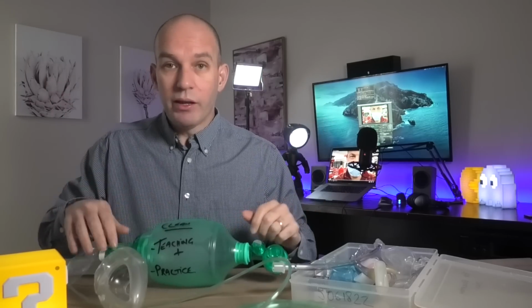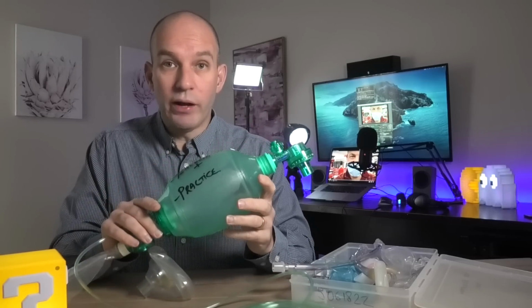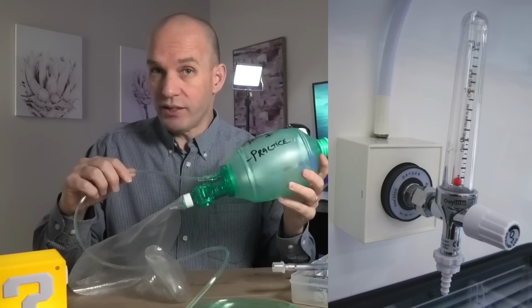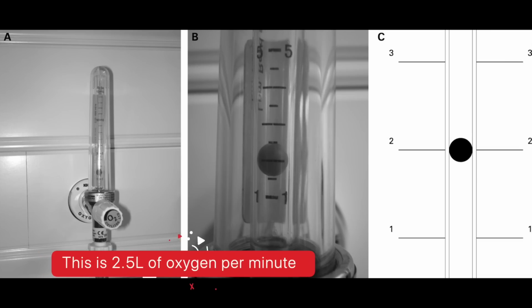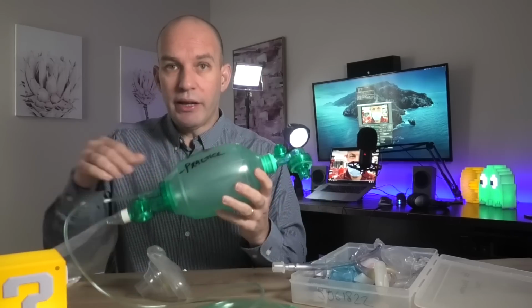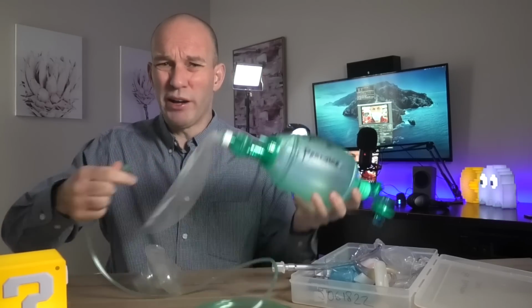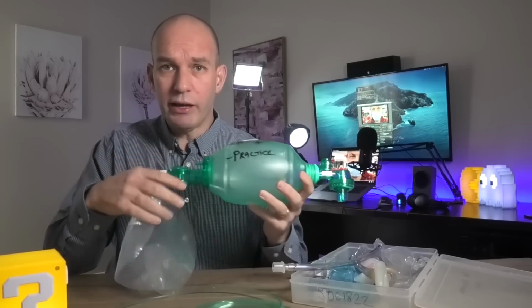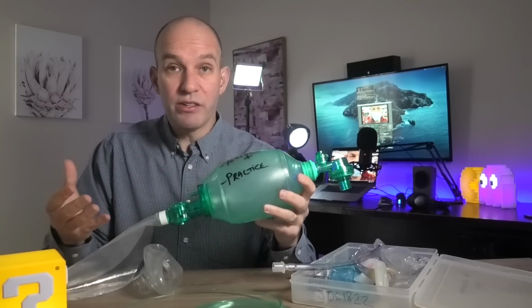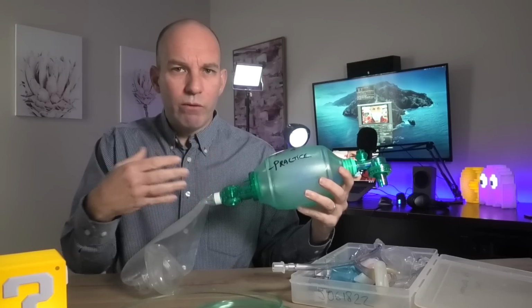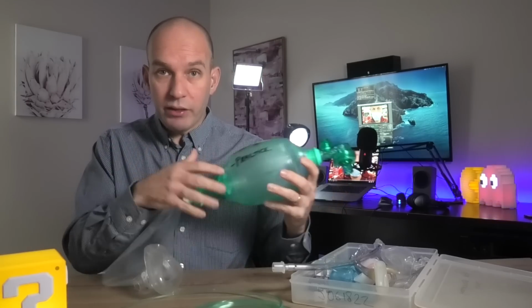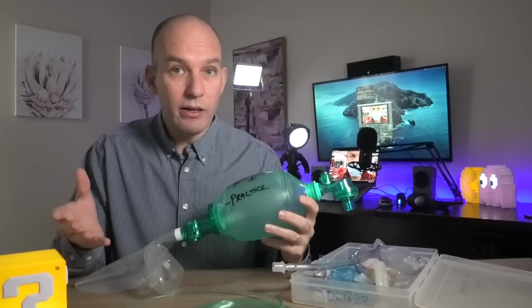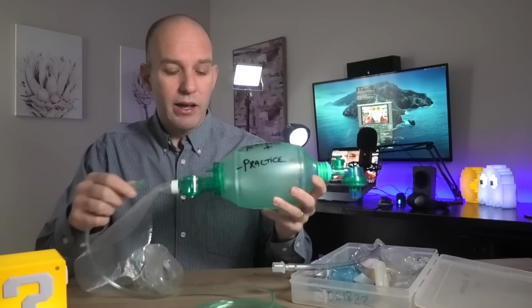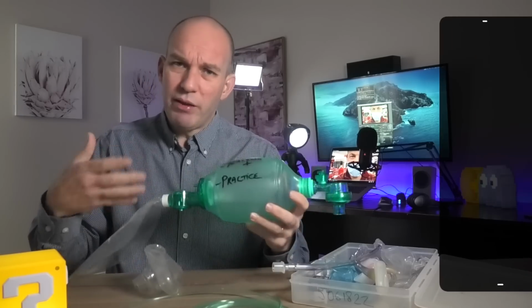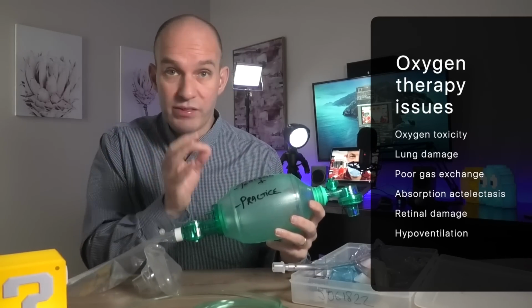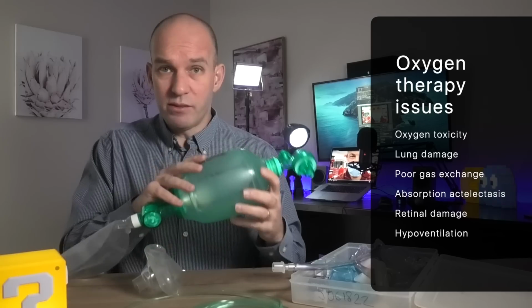And so if we were to mechanically ventilate a patient for a day using oxygen off a wall or a cylinder, and we dialed it down as low as we possibly can, but remembering this thing works on not only air coming into it, but also a mixture of oxygen. And sure, I could disconnect that and just have pure room air going in. But that's not ideal because patients haven't got very good exchange of oxygen going into the body right now. So they need a little bit of oxygen, not 100%, but they need oxygen over and above what's in the air. And so we need to plug this in, and we need to be able to control precisely the amount of oxygen going to the patient. And this system doesn't actually help that.